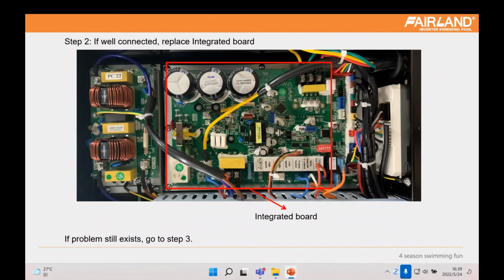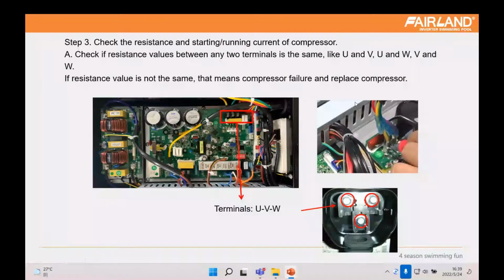And if the wire connection is fine, then we will try to replace the integrated board, because as per our experience, the compressor really has very stable quality. So most of the time, we need to prepare an integrated board to replace this. And of course, you can do some detection on the compressor. We will check the resistance between any two terminals, U and V, V and W, and U and W. If they have the same figures, the same numbers, that means the compressor is not short circuit.